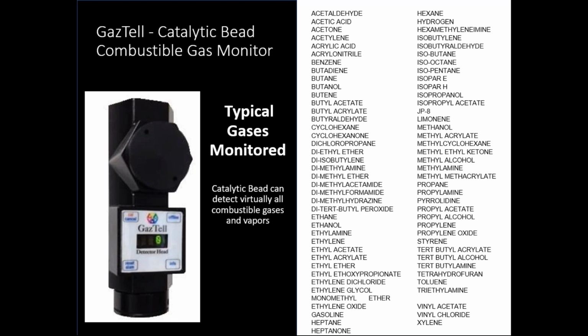You're also making sure that, because you're calibrating it with methane and it detects methane, you're proving that the sensor can detect all of the other gases that you might want to use the sensor for. For example, gasoline has an ignition temperature of about 535, I think, somewhere in that vicinity. Methane's ignition temperature is 999. This means if you've proven that it can sense methane, then you guarantee that gasoline can also burn on that same element, because its ignition temperature is much lower than methane.